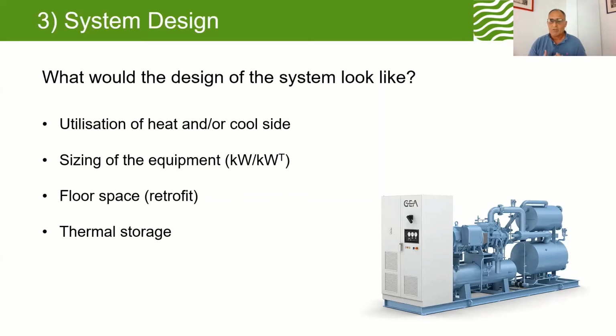The sizing of the equipment can be difficult. Coming from a gas world into a heat pump world, the numbers may not match up as you'd expect. Jared mentioned thermal storage, which can be hard to get your head around. If I turn on a hot water service at home and turn on the shower, I get instantaneous hot water, but a heat pump usually doesn't approach things that way. It's a longer period of taking heat from the atmosphere and putting it into my water storage unit, and I might hold that until it's more beneficial to use the hot water at a different time of day.